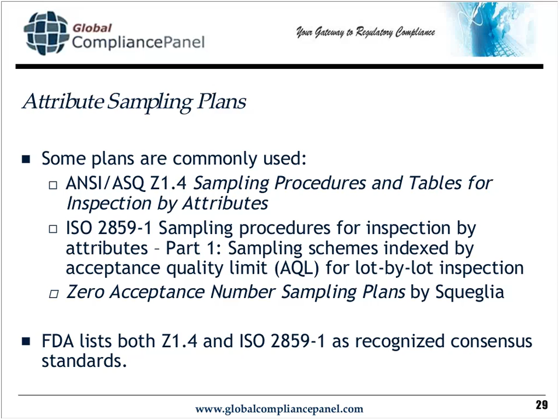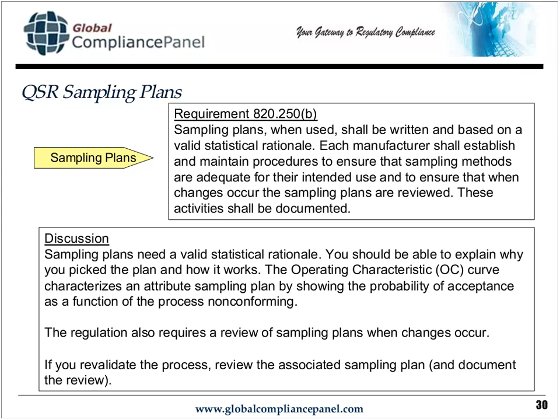Now, when you do sampling plans, however, there are some requirements in the QSR. And here it is. They've got to be written and based upon a valid statistical rationale. You have to have methods to make sure that they're adequate for their intended use, and that when changes occur, the sampling plans are reviewed. So this is very important. What's going to happen in validated processes is that if you make a process change or you have a deviation, you have to go back and decide whether or not you need to revalidate your processes, and you should be looking at the frequency at which you are looking at input parameters. In addition, if you have a sampling plan, you should be looking at whether or not the sampling plan is giving you the level of protection that you need. And we're going to talk about that when we talk about the operating characteristic curves. It's going to give you some understanding of the level of protection that you get. In other words, the risk that you're taking by doing sampling.